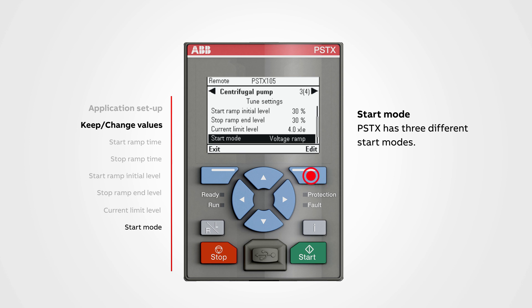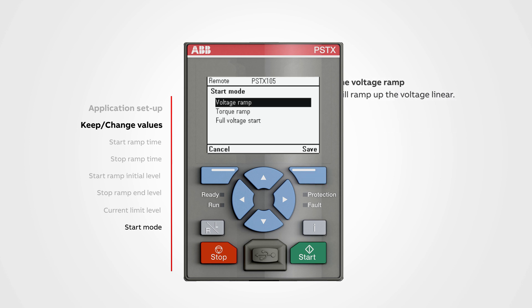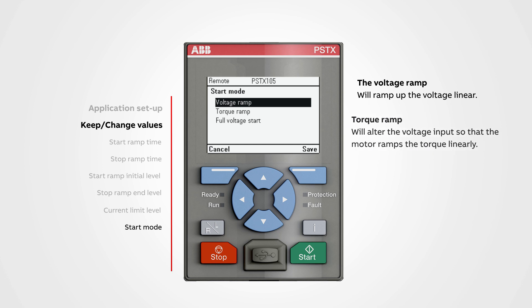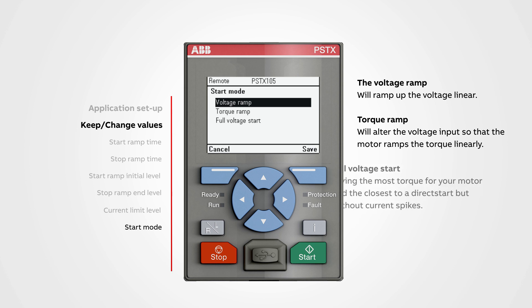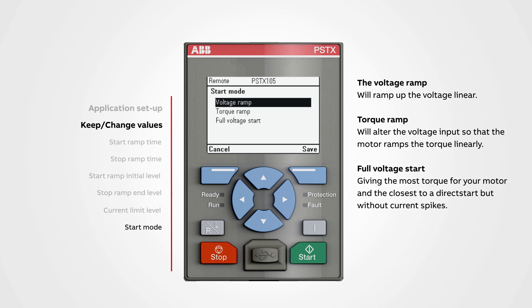Start mode: PSTX has three different start modes. To change the setting, push edit. The voltage ramp will ramp up the voltage linearly — the most common ramp for soft starters. The torque ramp will alter the voltage input so that the motor ramps the torque linearly; this ramp will start the motor more gently. The full voltage start is the most powerful, giving the most torque and the closest to a direct start but without current spikes. Use the navigation buttons to change the value, then push save.